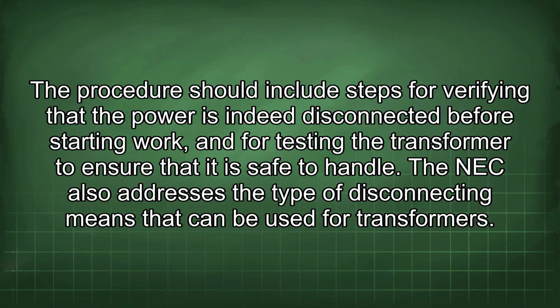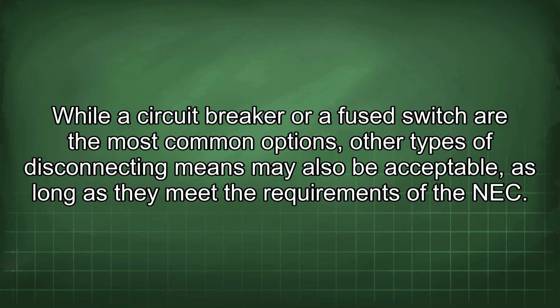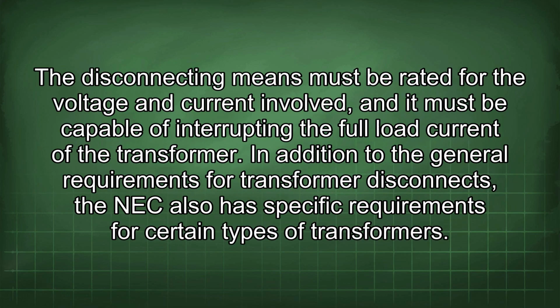The NEC also addresses the type of disconnecting means that can be used for transformers. While a circuit breaker or a fused switch are the most common options, other types of disconnecting means may also be acceptable, as long as they meet the requirements of the NEC. The disconnecting means must be rated for the voltage and current involved, and it must be capable of interrupting the full load current of the transformer.